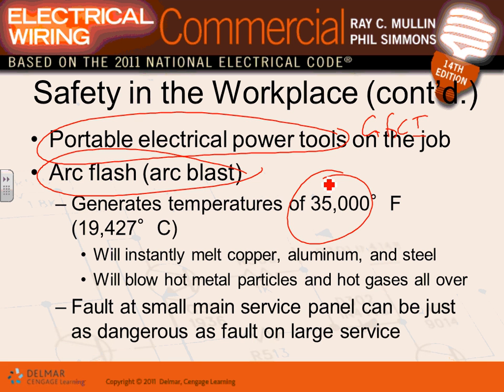This is what we used to scare the electricians when they're working on the equipment, guys. The building that you're going to be doing right now in the commercial project is, I believe, 500 to 600 amp, 208/120. For the industrial project, it will be close to 4,000 amp. That's as high as you can get. You're opening a 4,000 amp, 480 switchgear. This is basically a suicide mission if you're not wearing your proper PPE.